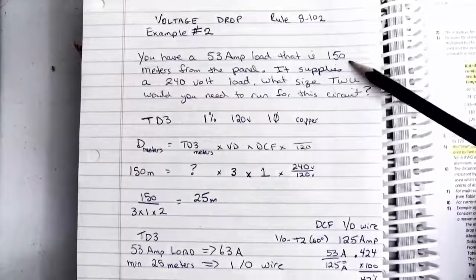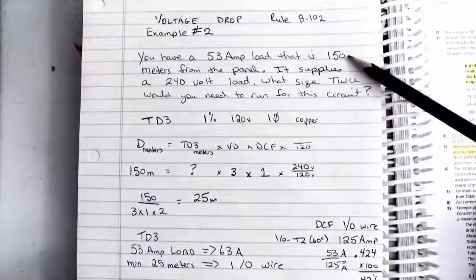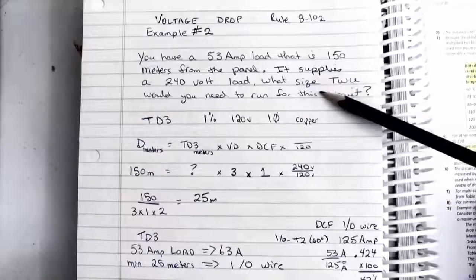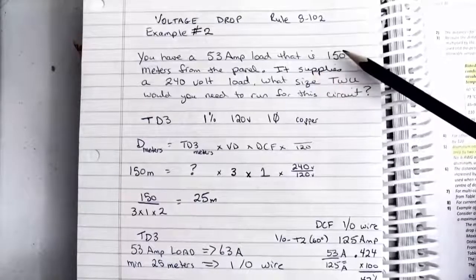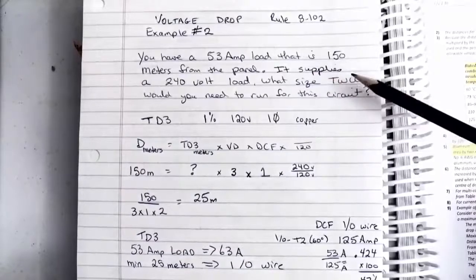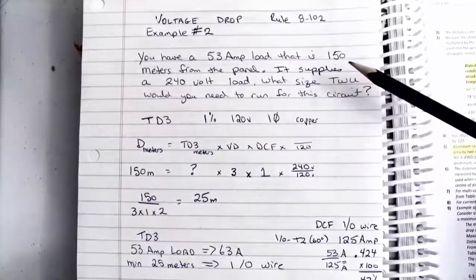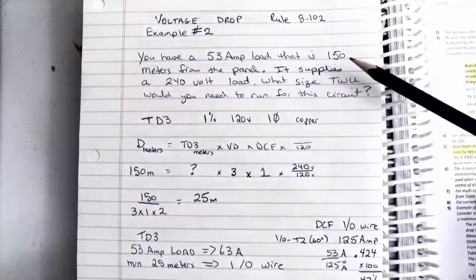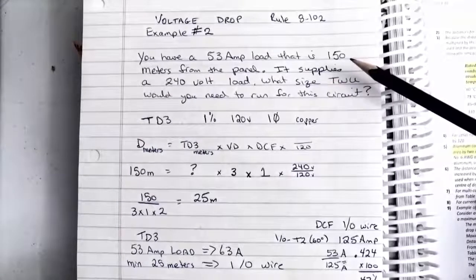This question specifically talks about supplying a load from a panel, so we know that's a branch circuit. When we look at voltage drop for a branch circuit, we know that we're allowed a maximum of 3% voltage drop.